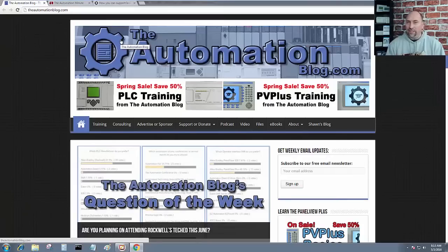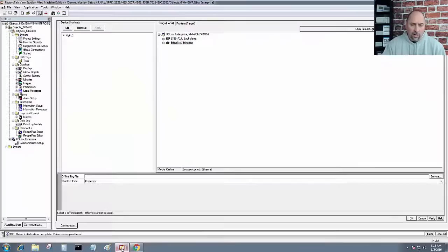Now, when you want to test the system out using your computer, in other words, you want to run View Studio to your PLC, well, the straight-through cable is not going to work anymore because both those devices are DTE. So you'll need either a null-modem cable or a null-modem adapter to convert your straight-through cable to a crossover cable. So 2-to-3, 3-to-2, 5-to-5. So that's number one. You've got to have the right cabling.